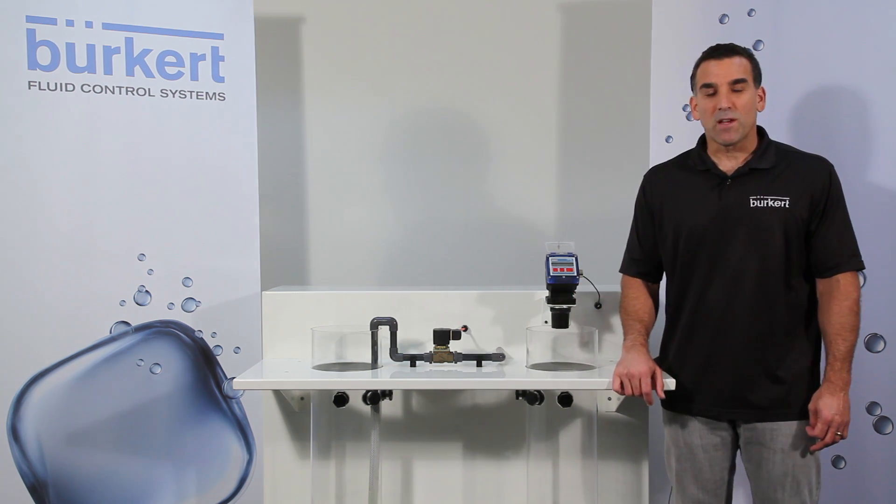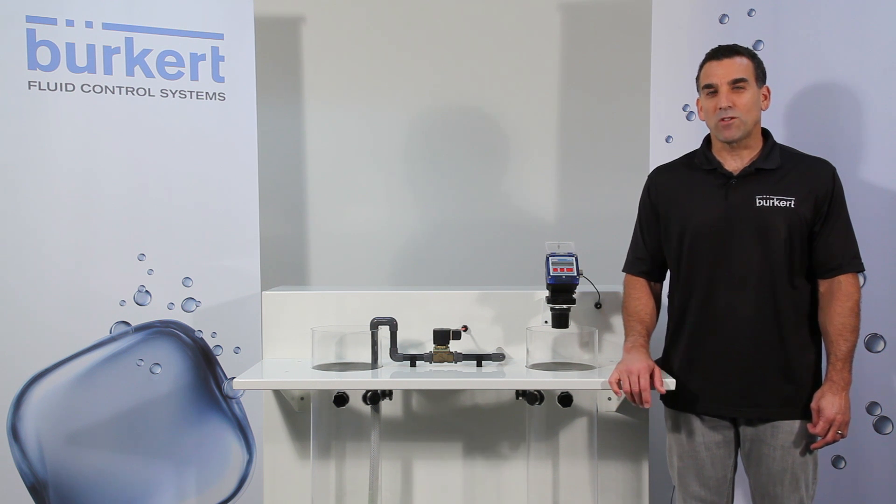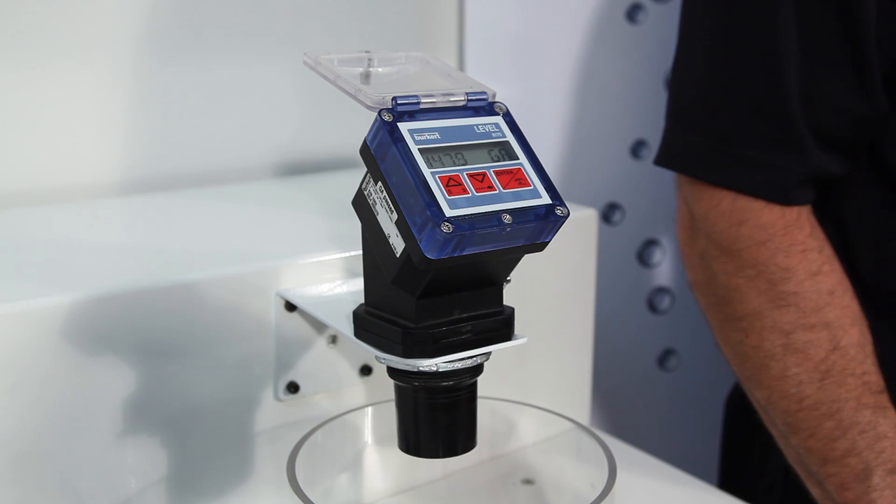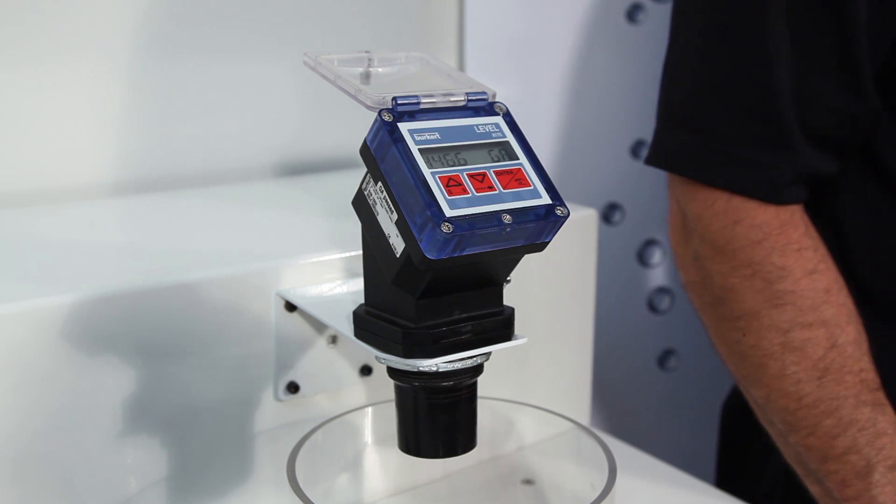Here we have our Type 8175 Ultrasonic Level Transmitter and today I'll be showing you how to perform a volume teach-in for any size or shape tank without actually having to fill or empty that tank. You can perform this with as little as 2 points or as many as 12 points as long as you know a few determined distances and associated volumes of the tank.